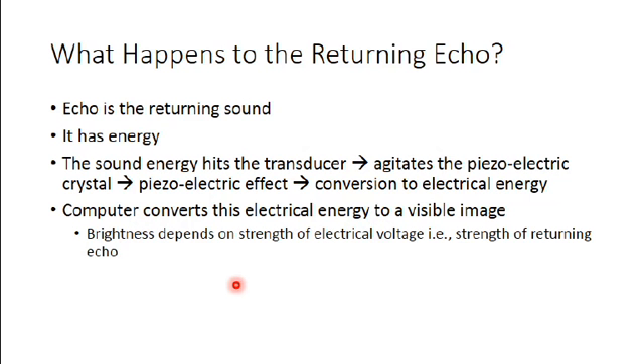The brightness of the image depends on the strength of the electrical voltage that is generated. And the strength of the electrical voltage that is generated in turn depends on the strength of the returning echo. So the stronger the returning echo, the higher will be the electrical voltage, and the brighter the image will be. So I repeat, the stronger the returning echo, the higher the electrical voltage, and therefore the image will be brighter.